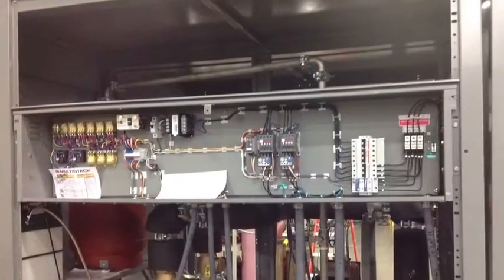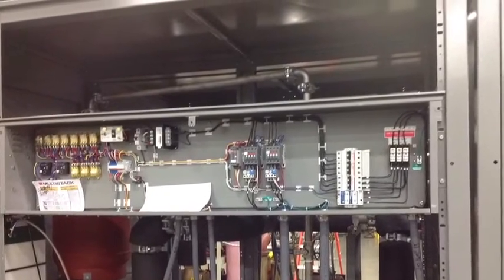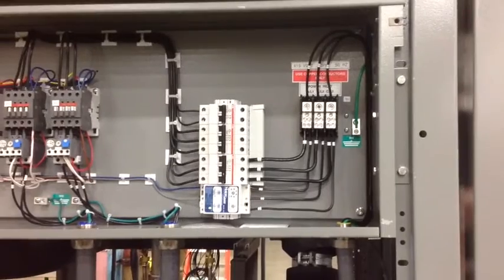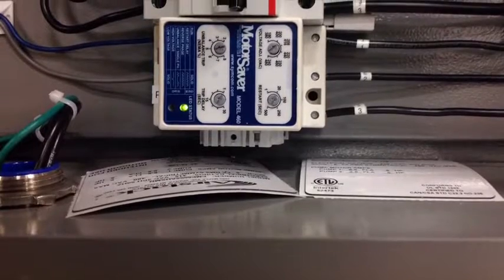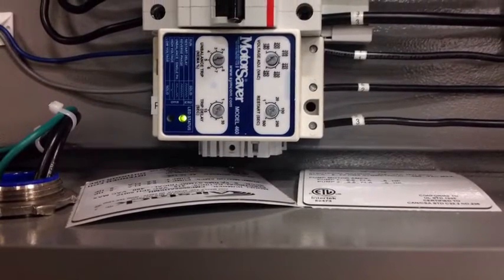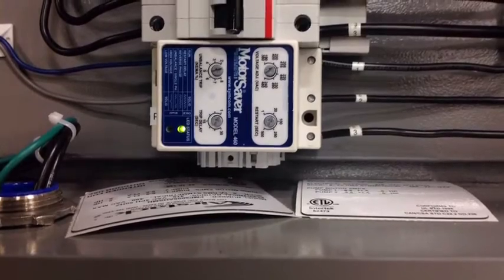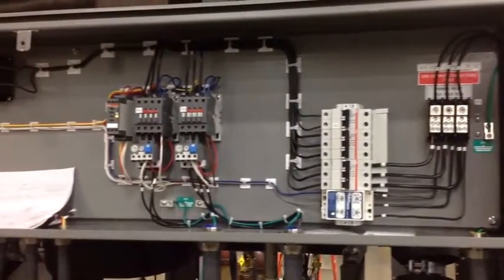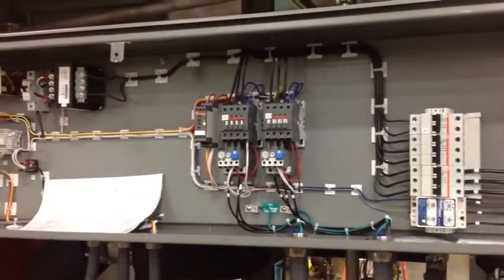And now for a tour of the pump cabinet. Again, power comes in and works its way right to left. You can see the control circuit breaker on top, the 2-pole breaker, and then 2 individual 3-pole breakers for pump 1 and pump 2. That was a close-up of the power phase monitor.